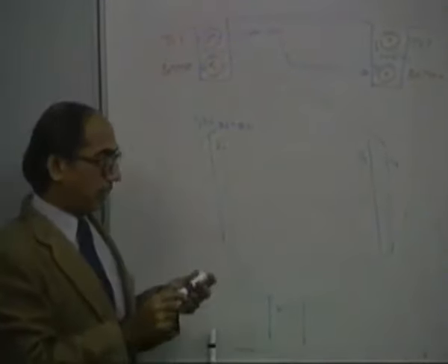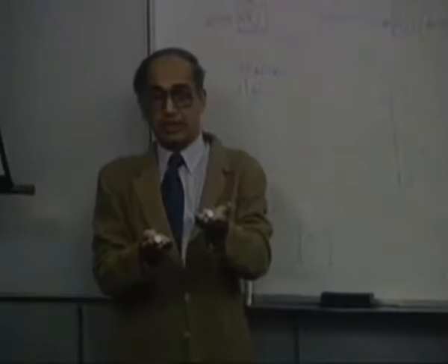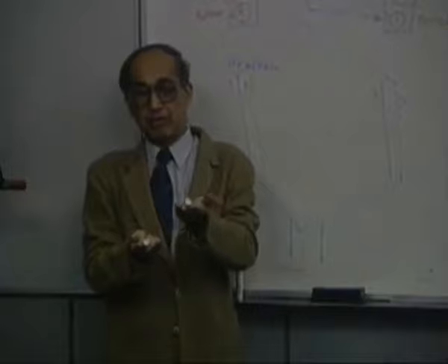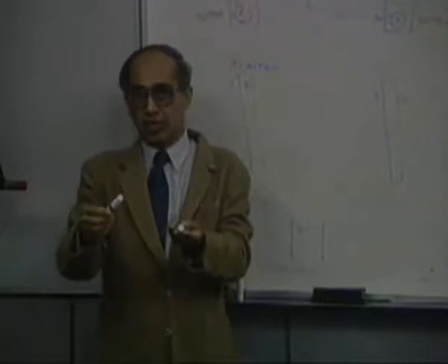So this is what is known as a double layer winding, and you ask why we do it like this. Usually if in a coil one side is top and another is bottom like this, and you place it symmetrically around the periphery of the armature, there will be one top, another bottom, next top, another bottom like that. Then in the end winding there will not be unnecessary overlap connections, so it will fit in properly.